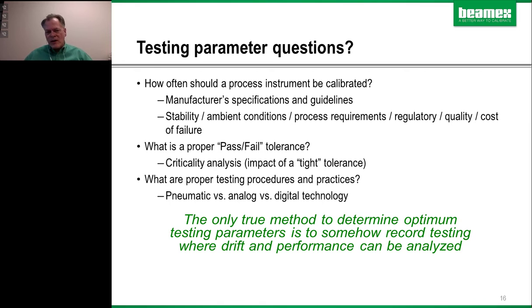All right, so let's talk about one other parameter or area for calibration, the different testing parameters. So one thing that you guys have to figure out is how often should an instrument be calibrated. The manufacturer might have some guidelines, but really you need to look at specifications. How stable is the instrument over time? How much does it drift? How varied are the ambient conditions? Is it in an air-conditioned part of the plant, or is it an area that's outdoors? And then how demanding is your process? And all this could be moot if there's some auditor coming in and looking at something. They may mandate that you test something on a regular basis. And of course, you need to look at what does that instrument cost you if it's not measuring accurately.